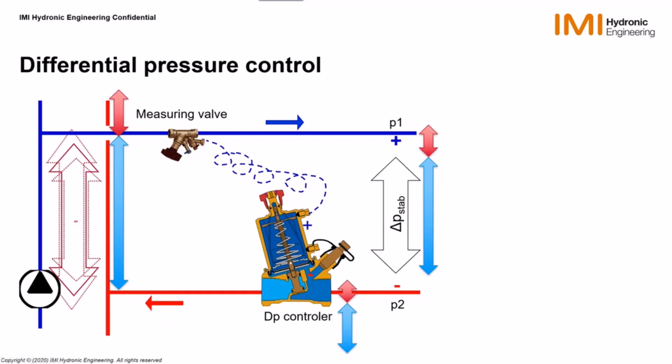So basically the mechanism will go down, compressing the spring at the same time until we get again a balance of force between the spring and the membrane at another but more closed position of the STAP, meaning that the STAP will therefore get in a situation of having closed itself more, increasing its own delta P, and by increasing its own delta P, it decreases the delta P stabilized back to where it was, or almost back to where it was.